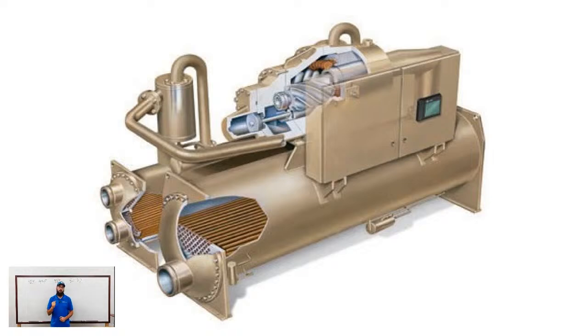You do not want that compressor cycling. The majority of your energy usage happens at startup, so if you're constantly cycling, you use a huge amount of energy to get that thing turning and get the refrigerant moving. So one of our main goals is to make sure that we're just not doing that. We do that by having really precise load control.